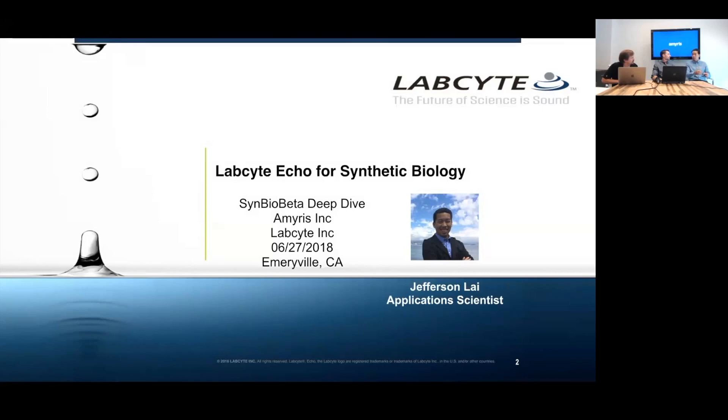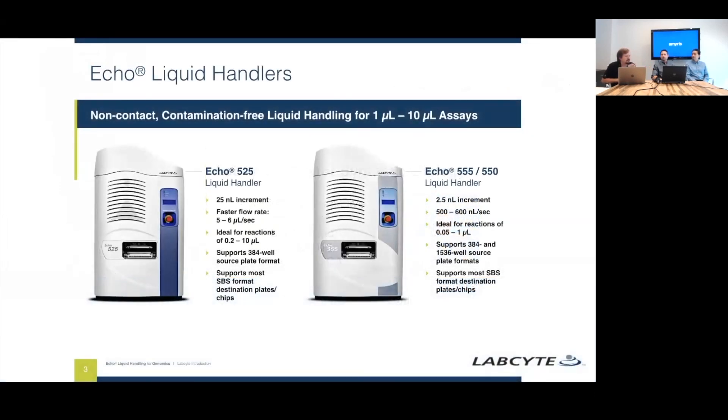You can now hit-pick exactly what you need and put it on the end. Just to give a quick overview: we produce two to three different models right now, as well as the new 655T. The ECHO 525 is the most popular in synthetic biology — it transfers 25 nanoliters at a time with a flow rate of about 5 to 6 microliters per second, and it's good for transferring master mixes, reagents, and precious samples such as DNA. Our other instrument is the 555T, which transfers 2.5 nanoliters — a much smaller droplet size.